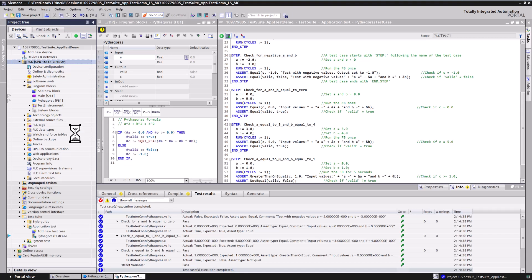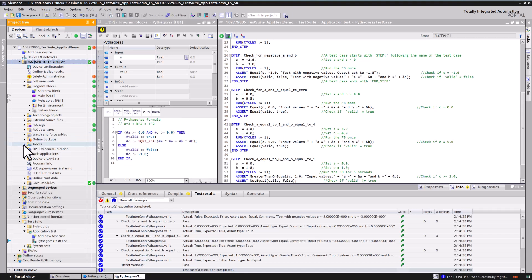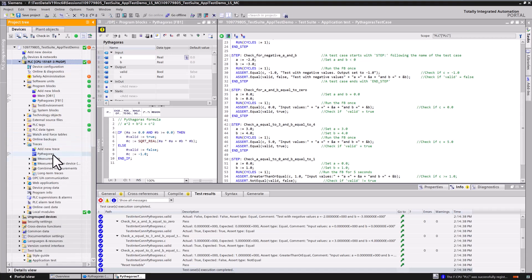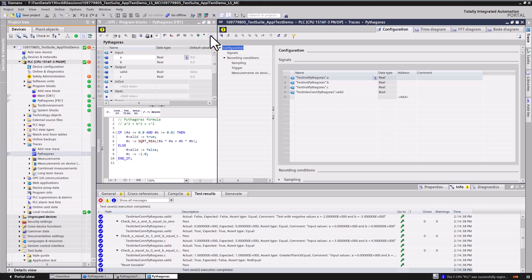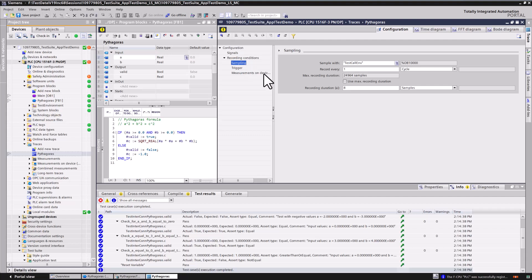Besides performance improvement, the new execution mode gives the possibility to go online and record a trace while running application test. The trace has been configured to record input and outputs of the Pythagoras function. Every test step runs one cycle so that eight PLC cycles as record duration are sufficient in this example.